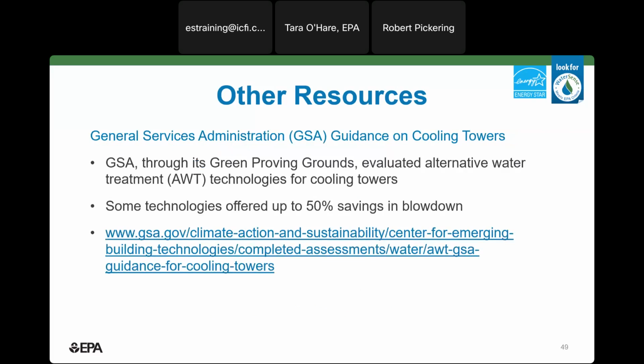Another great resource that is available is from the General Services Administration through their Green Proving Grounds. The GSA, obviously a big property owner, they evaluated a number of alternative water treatment technologies for cooling towers to try to validate vendors' claims on savings, efficiency, and other benefits. GSA summarized their findings in a detailed report. I think they looked at 4 or 5 systems, and some of them have really significant potential to reduce blowdown and increase cycles of concentration. So I look to this as a really great independent source on kind of validating some of those claims and looking for some unique opportunities to improve the water efficiency of your tower.